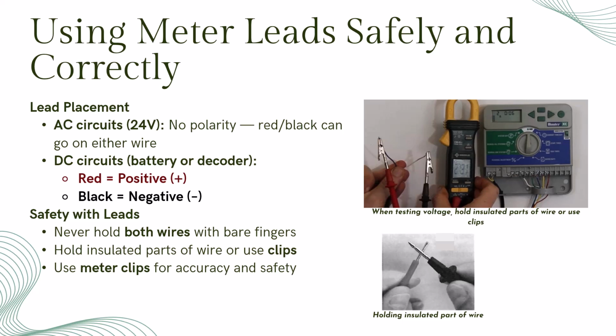Lead placement is another key factor in getting accurate readings and staying safe. In standard irrigation systems, valve circuits run on about 24 volts AC, which has no polarity. That means it doesn't matter which lead, red or black, you put on which wire. However, when you're working on battery-operated controllers or DC decoder systems, polarity matters. Always place the red lead on positive and the black lead on negative terminals or wires.